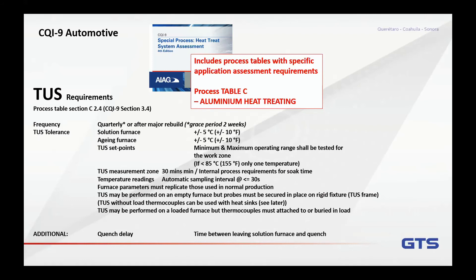The furnace parameters need to replicate what you would normally use for production for the manufacturing step — make sure you're comparing like for like. If the furnace is empty, you must do the survey on an empty furnace; if it's loaded, you do it on a loaded furnace. Whatever you choose, you then use the same conditions going forward for subsequent TUSs.